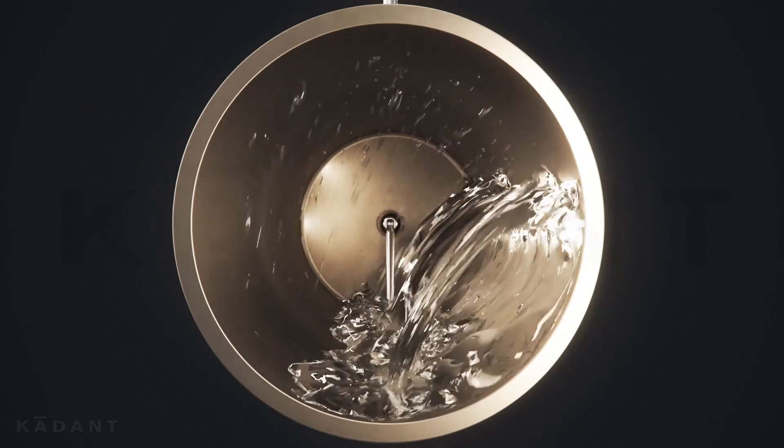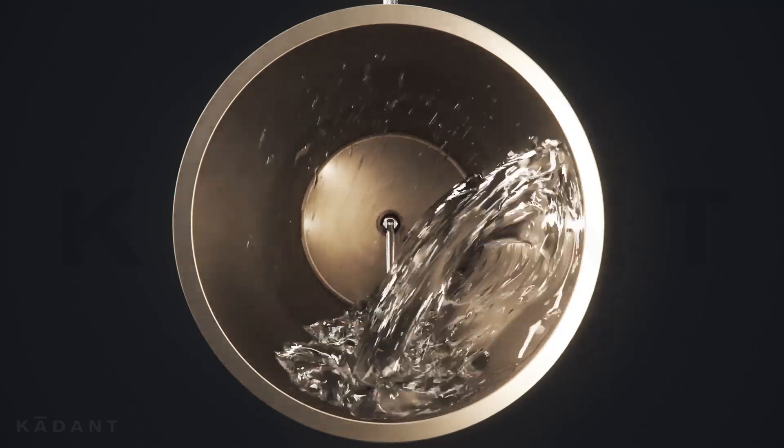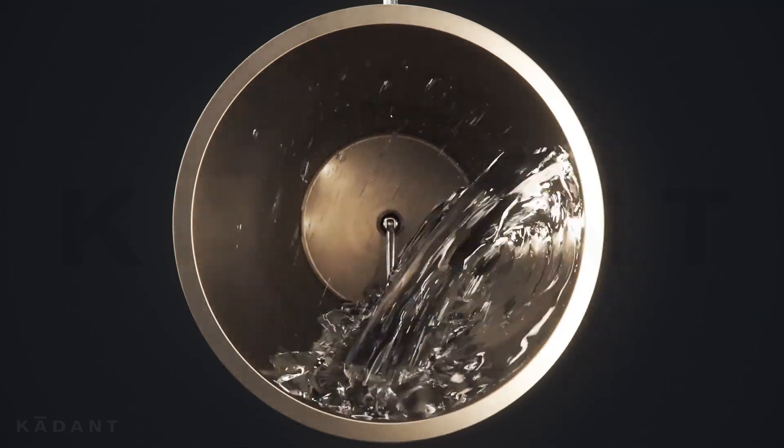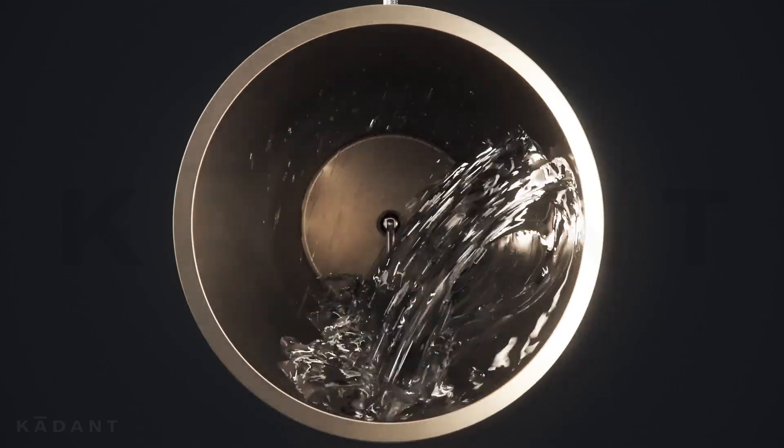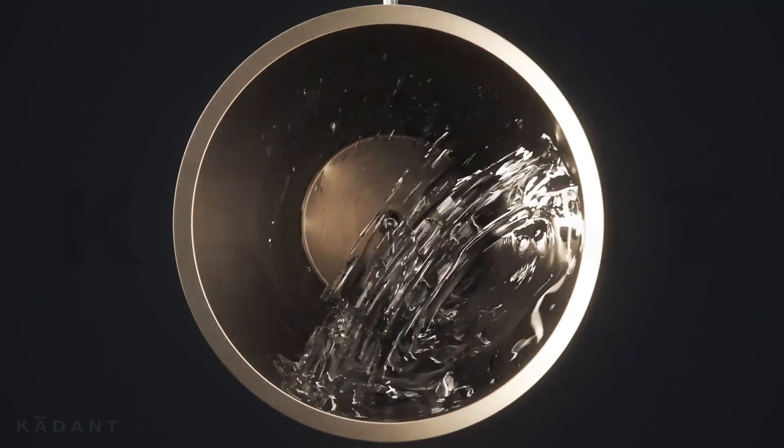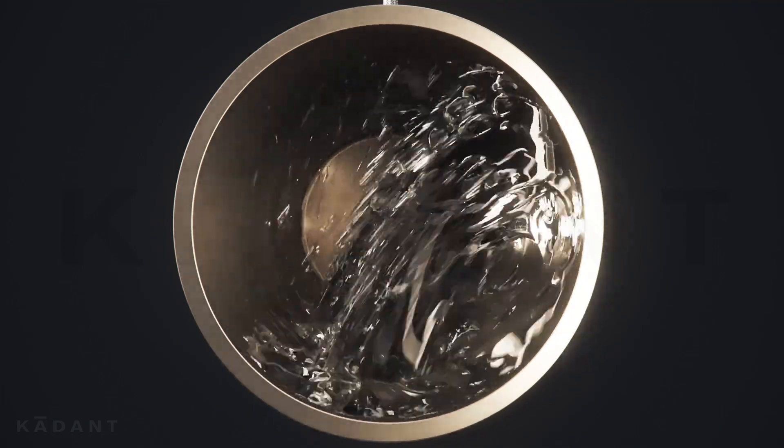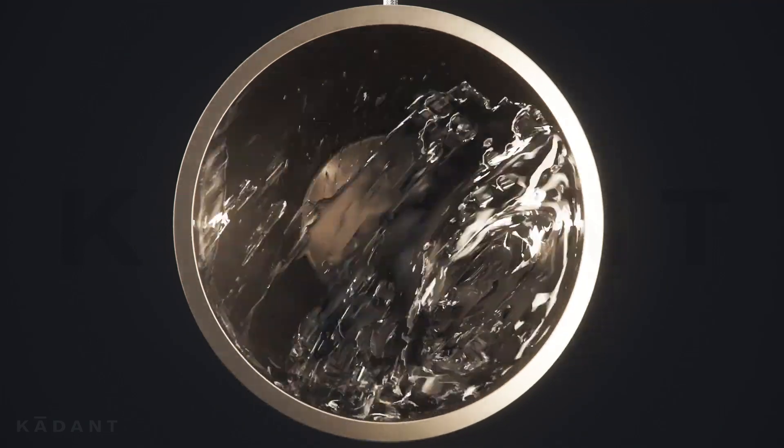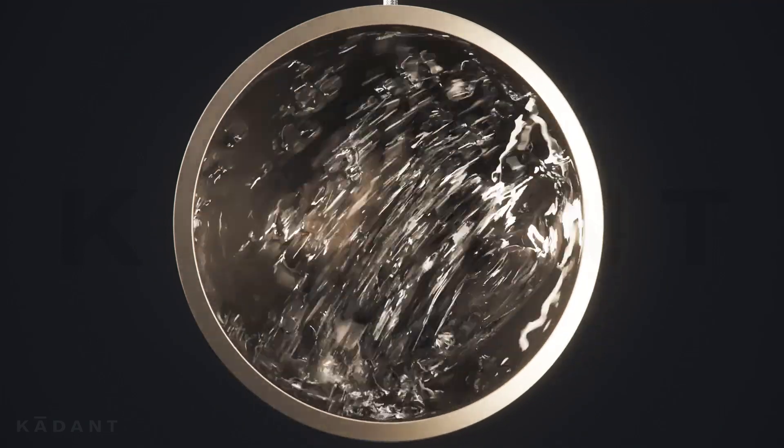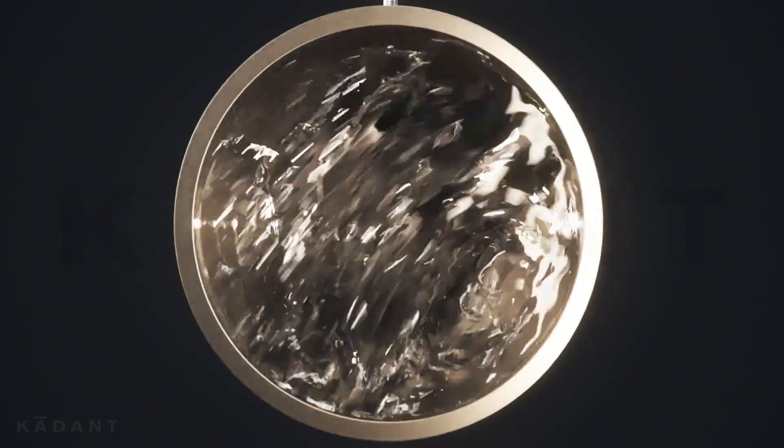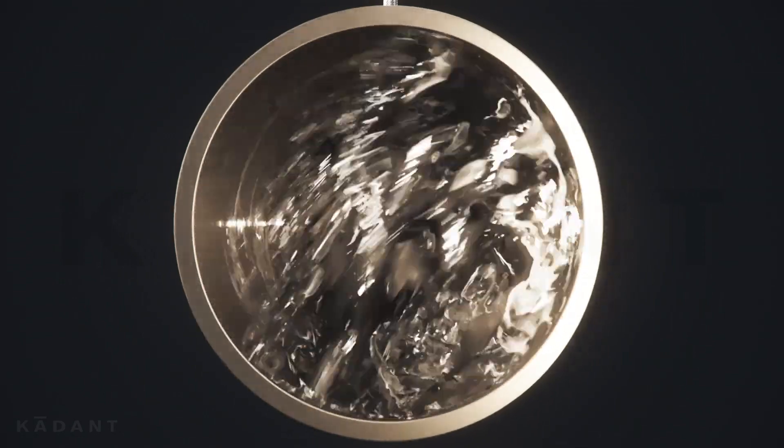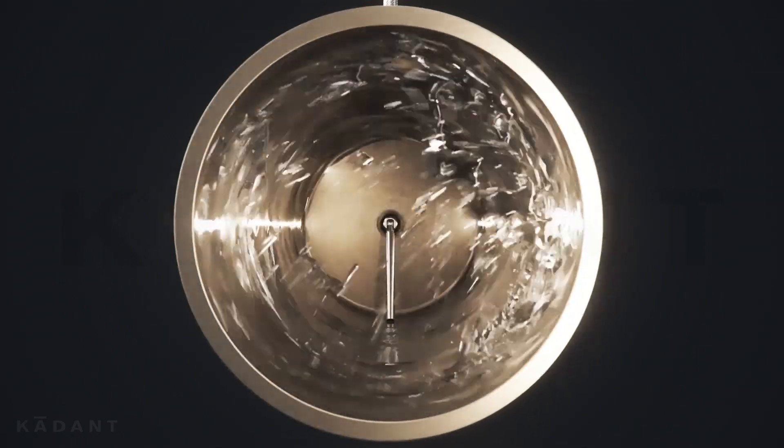Accurately positioning and holding the siphon in place is key to efficient and even heat transfer. If the siphon is too close to the roll's wall, the condensate layer becomes too thin and will begin to rim, forming an insulative layer.